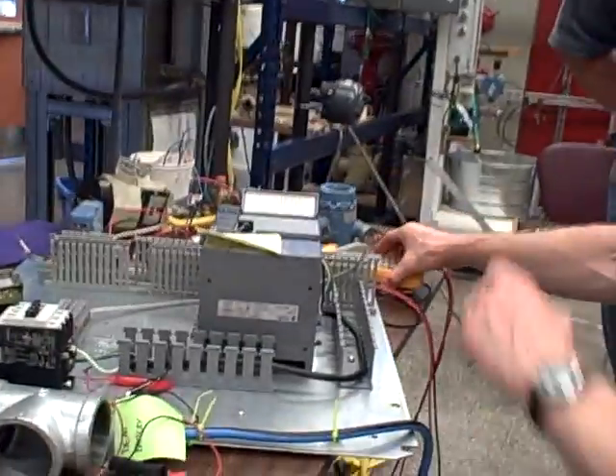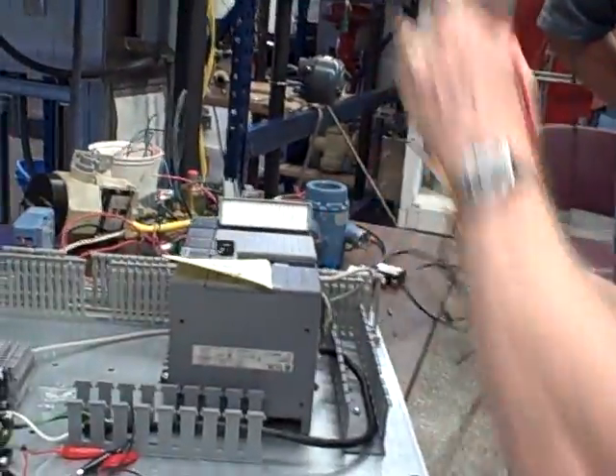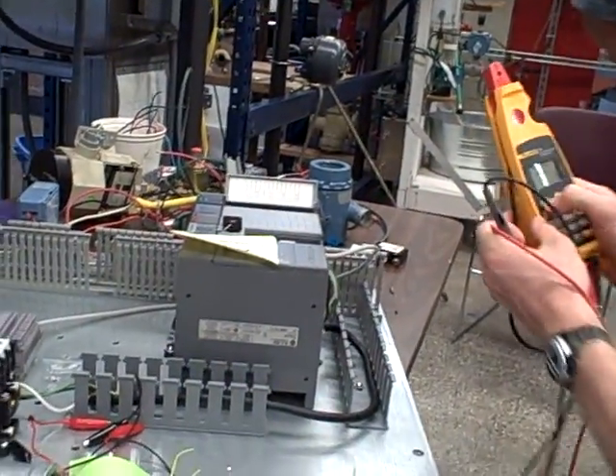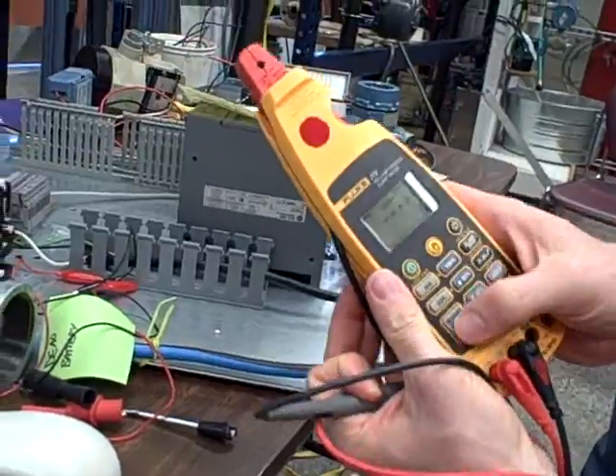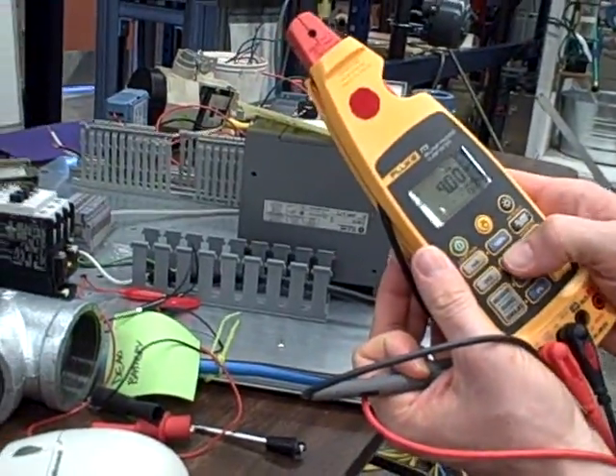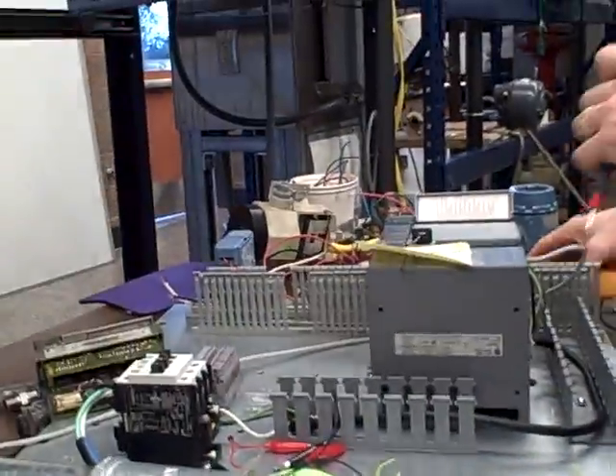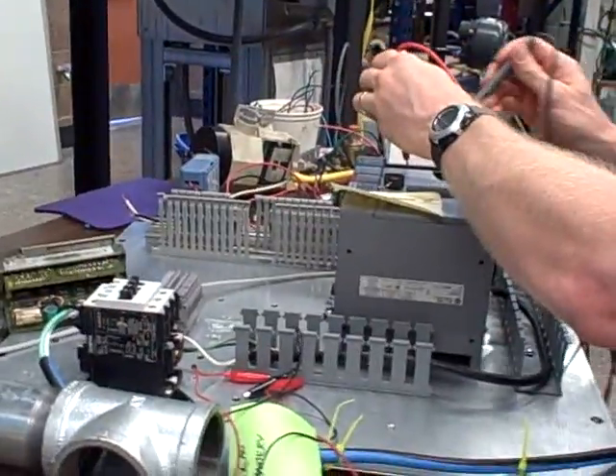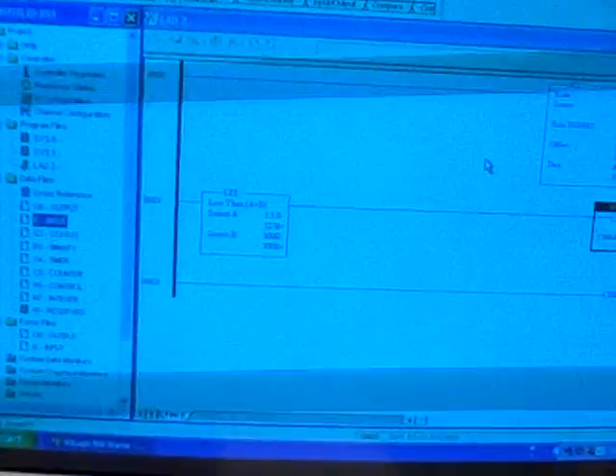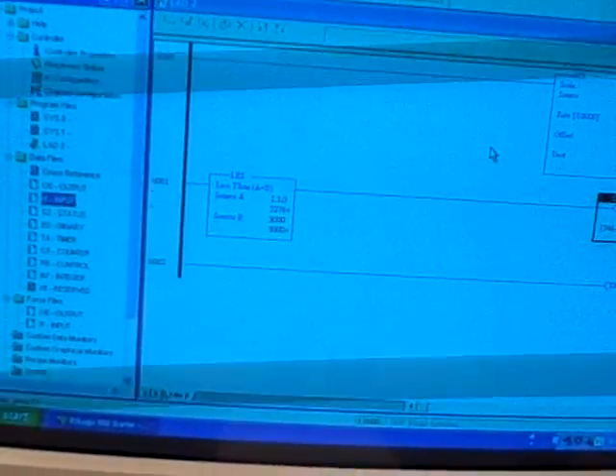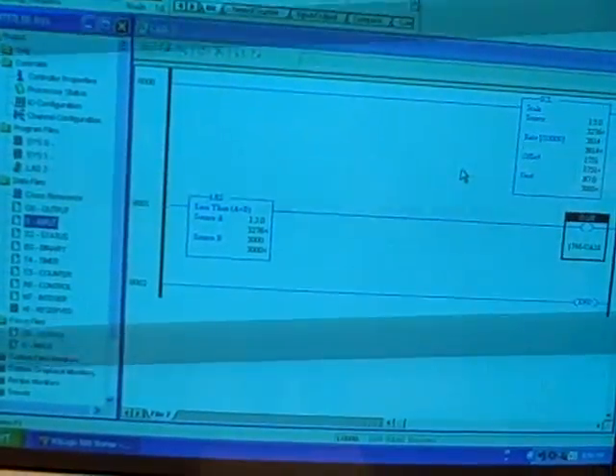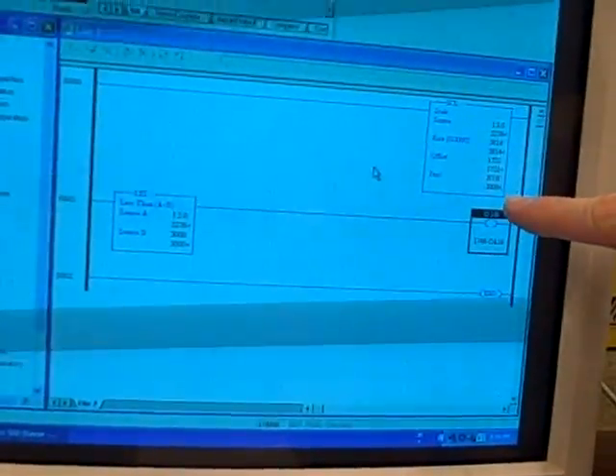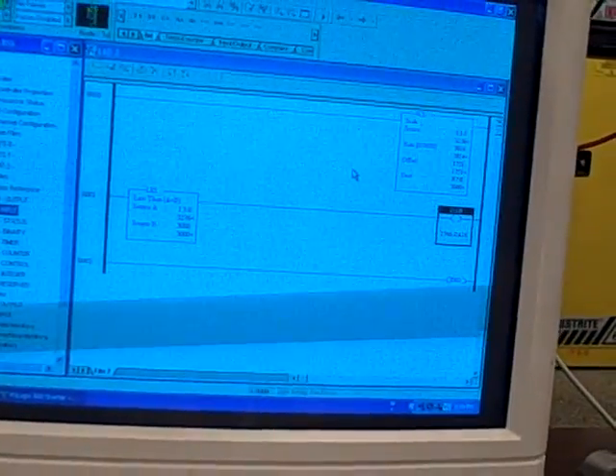Over here, what I'm going to do is hook up my current source again. This is my Fluke current source. Set it for sourcing milliamps. I'll go to 4 milliamps right here, connect it to channel 0 on the analog card. And there we go, channel 0, and you see right there our destination address inside the scale box is reading 3,000. That was going to be 30 degrees. That's fixed point notation, 30.00, so 3,000.